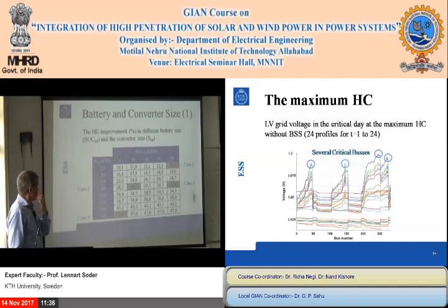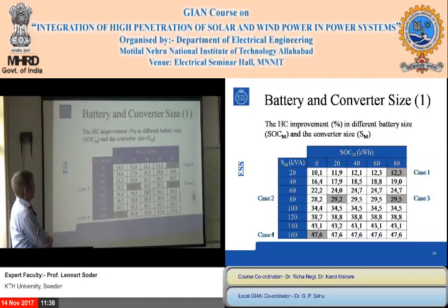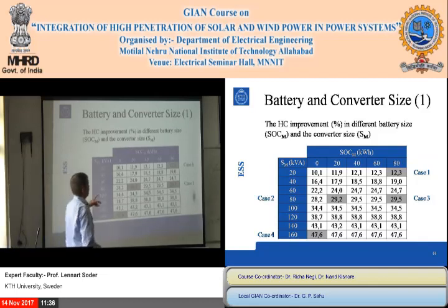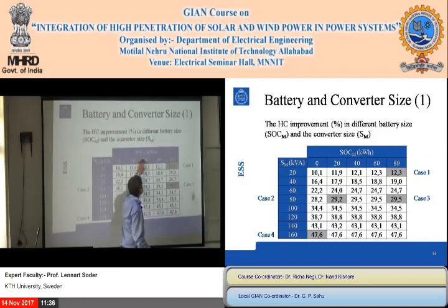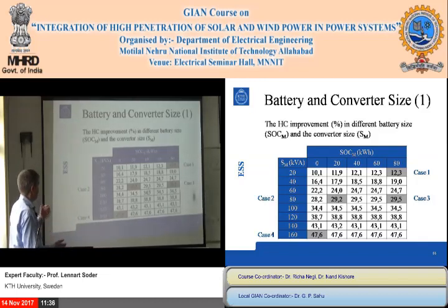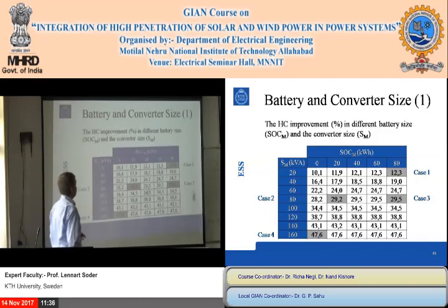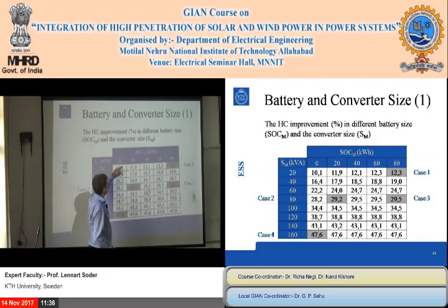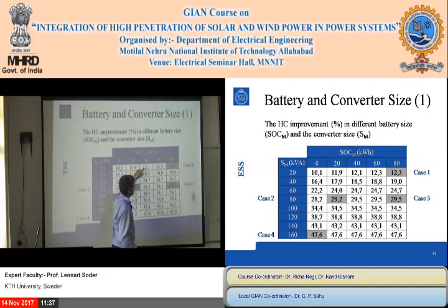So this was the result: the hosting capacity improved by battery size. Here you have the battery sizes, and these are converter sizes. The question was how much you could improve the hosting capacity compared to a base case when you don't have these kinds of things. And you can see here that yes, you started with a 10% increase if you have a small converter here, but if you increase the battery size, you will slightly increase the hosting capacity.